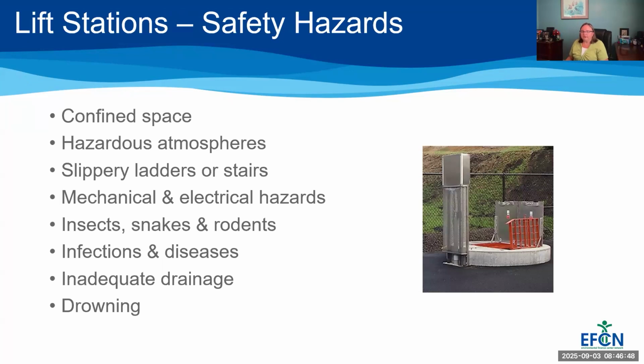Last thing about lift stations are safety hazards. Lift stations do have several safety issues. So they are a confined space. They can have hazardous atmospheres. The gases that are in a lift station can be even deadly. I mentioned the ladders being slippery or even not stable. There's mechanical moving parts. There's electrical hazards. Of course, insects, snakes, rodents, they like to hang out in lift stations. Infections and diseases can always be a concern when you're working in wastewater. There can be inadequate drainage around your valves, in your valve boxes, and potential drowning.